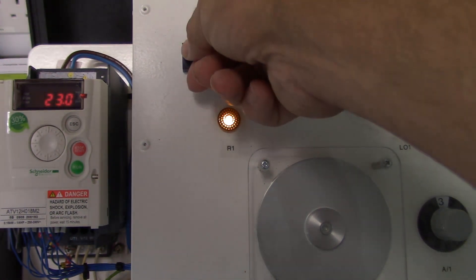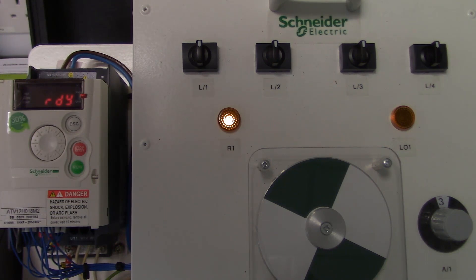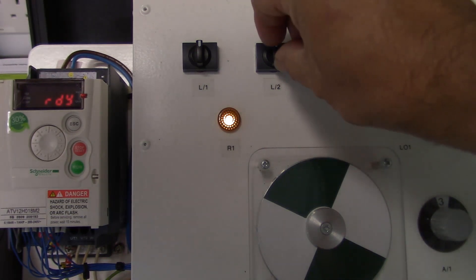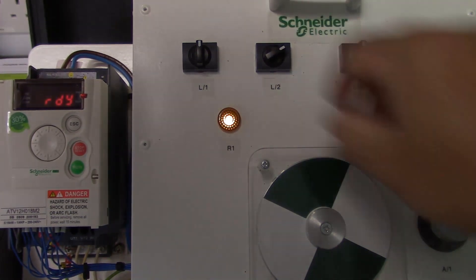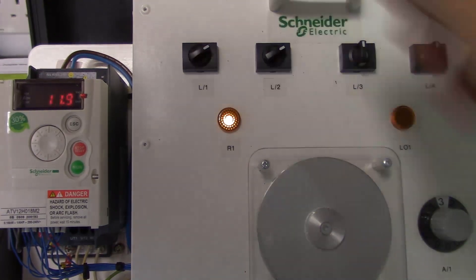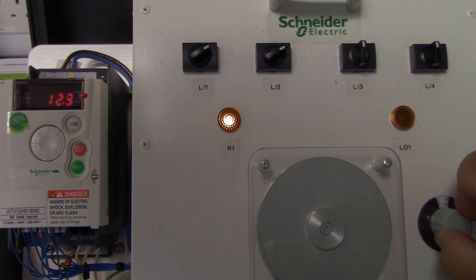If I now stop the drive and close logic input 2 I will now have manual control. The start and stop will be on the LI1 connection and the speed will be the analog input 1 from the potentiometer.